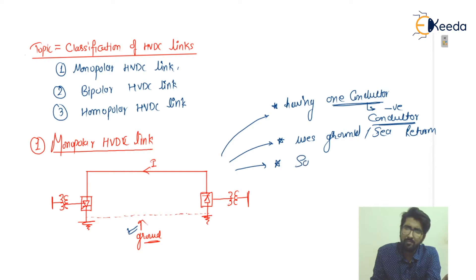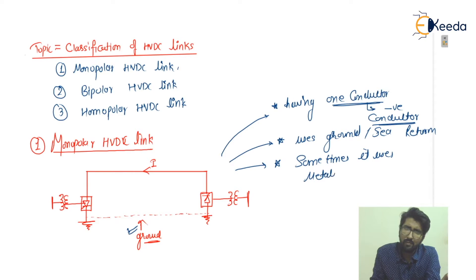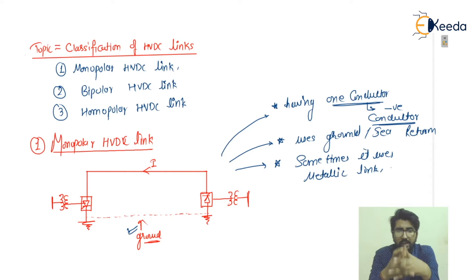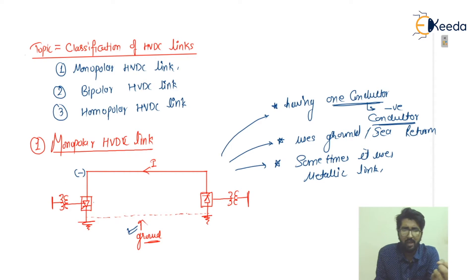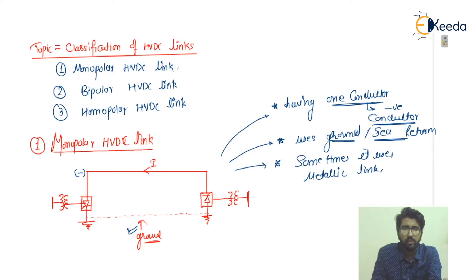The monopolar HVDC link uses ground or sea return. Sometimes it also uses a metallic link or conductor. The key points to remember: it has only one conductor which is a negative conductor, chosen for low corona effect, and current returns via ground or sea return.